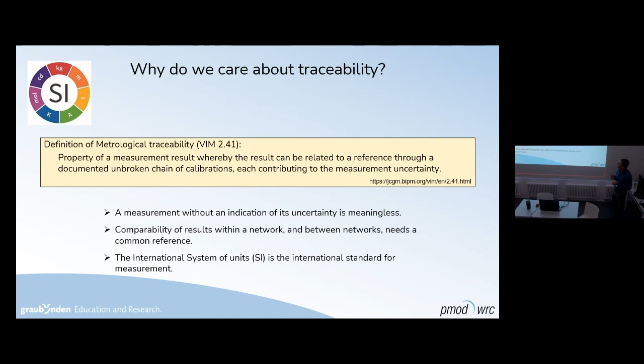And in our case, we are measuring radiation, and so we have traceability to different primary standards. But the idea is still the same. You can go back to a recognized primary standard. And a measurement without uncertainty is meaningless, because then you don't know how much you can trust it. You need that kind of comparability between measurements. So if you have a network and you have different stations located far away, the only way to be able to compare measurements from these different stations is if they have been calibrated to a common reference. And so that brings again the term of traceability and calibration. And the recognized unit for measurements is the International System of Units, abbreviated SI, as you all know.